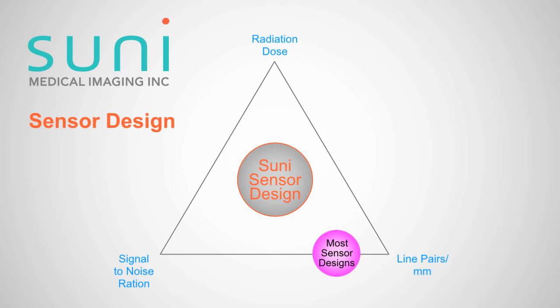The Suni sensor — coming back to your original question — is intentionally using larger pixels than many competing products, and there is one straightforward reason for it. The line-pairs-per-mm on a phantom is one thing, but you have to consider the actual objects in your oral cavity. If the smallest object in your oral cavity can be detected at, say, 12 line-pairs-per-mm, then the question is: do you really need a sensor that can detect 16 or 18 line-pairs-per-mm? The Suni design team decided to use intentionally larger pixels to gain headroom for optimizing the sensor for low-dose imaging.